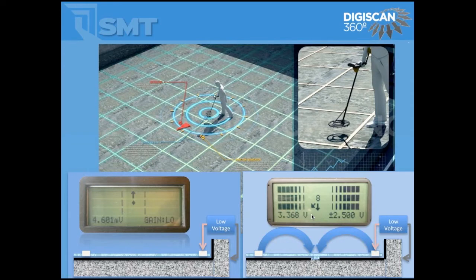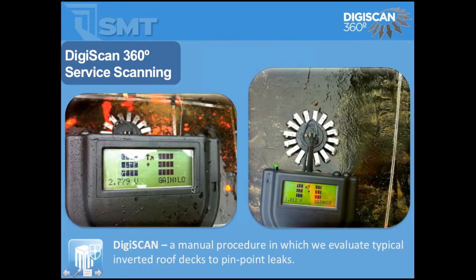If there are no holes within the area being scanned, you will have very little or no voltage and the direction will be highly variable. We have some videos — I'll send links for you to review, showing how we set it up, how we find holes, and how it's very similar to a metal detector. You make contact with the membrane, and as you move closer to the leak, the magnitude increases, as does the direction. As soon as you go past it, the direction comes back. Most people pick up on this in just a few hours of training.